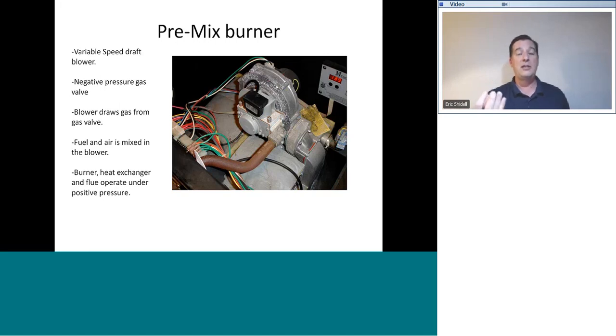It's very easy for manufacturers to tie a speed control onto that fan and boom, you've got a variable capacity throttling style burner. The faster that fan moves, the harder it sucks on the gas valve, the more gas and air are mixed together, and the bigger the fire is. The slower the fan moves, the less gas it draws in, the smaller the fire is. It's a modulating burner. Not all premixed burners are modulating, but it's very easy to make a modulating burner out of a premixed style arrangement.